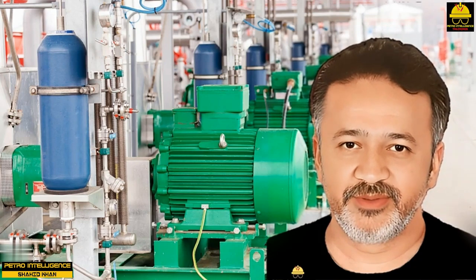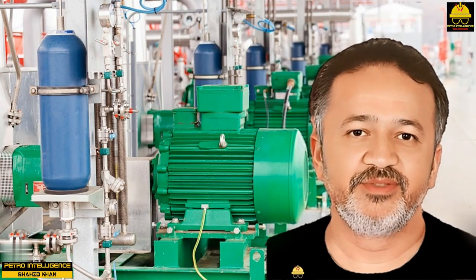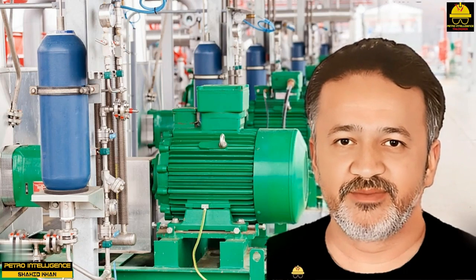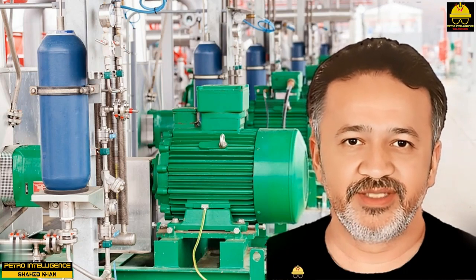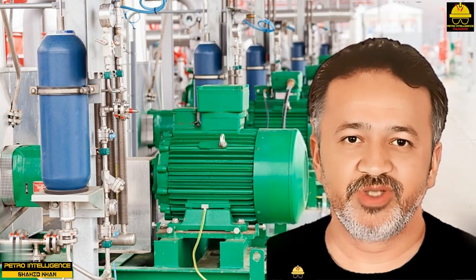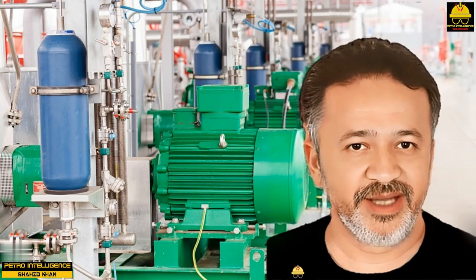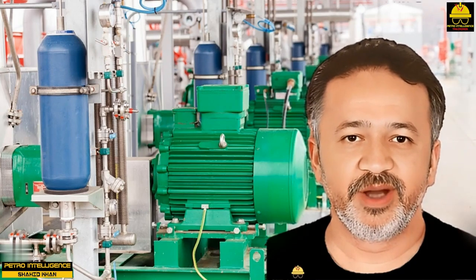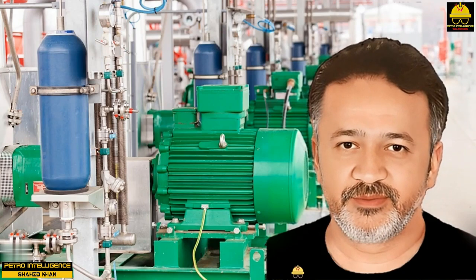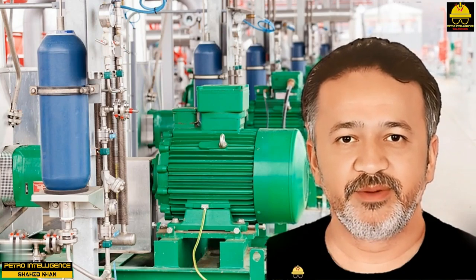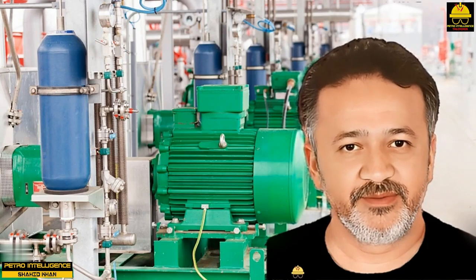Some vacuum pumps have an oil seal inside the casing of the pump. During the evacuation process, the process flow is drawn into the pump and discharged. Contaminants are trapped in the oil, which may require frequent changing. The primary cause for pump failure is contaminated oil.